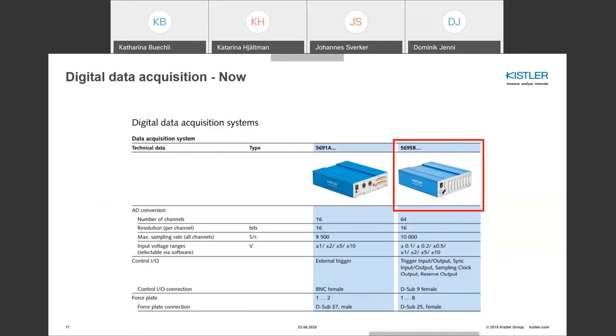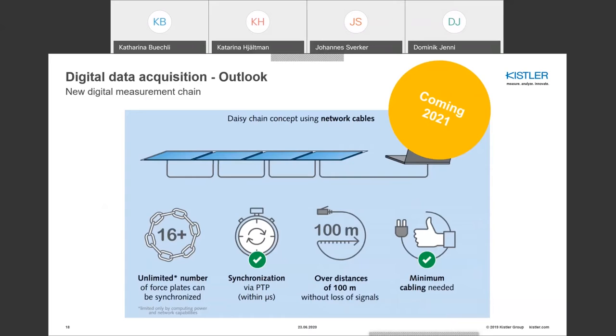Looking ahead to 2021, there will be a new digital measurement chain based on new digital force plates. The main advantage is that there will be no extra DAQ box — all force plates can be daisy chained. Up to 16 force plates can be daisy chained, and more can be synchronized via PTP switches, theoretically allowing an unlimited number of synchronized force plates. Synchronization uses the Precision Time Protocol (PTP), an industrial standard, with synchronization within microseconds. Cables are no longer limited to a certain distance — up to 100 meters without signal loss.